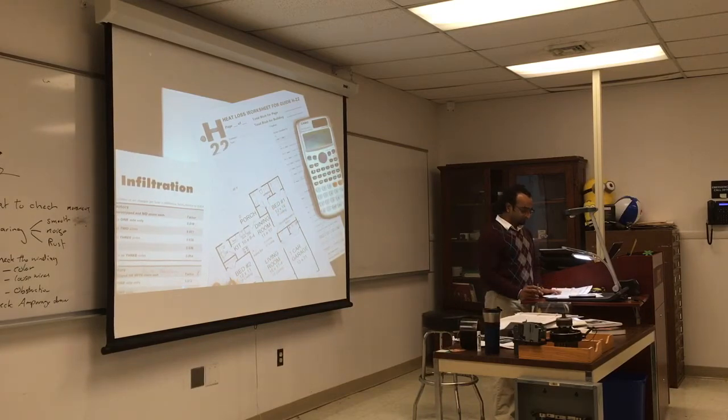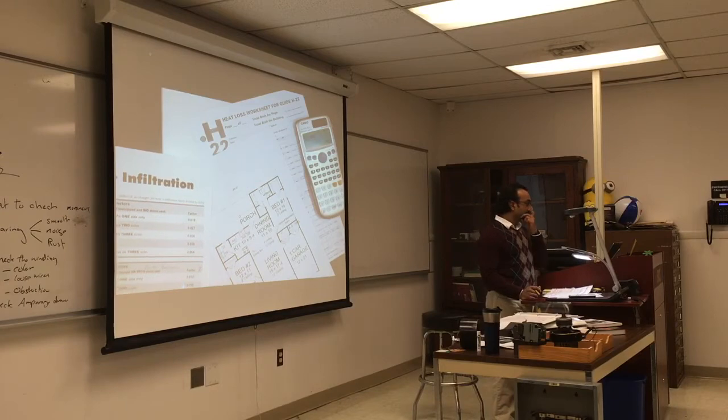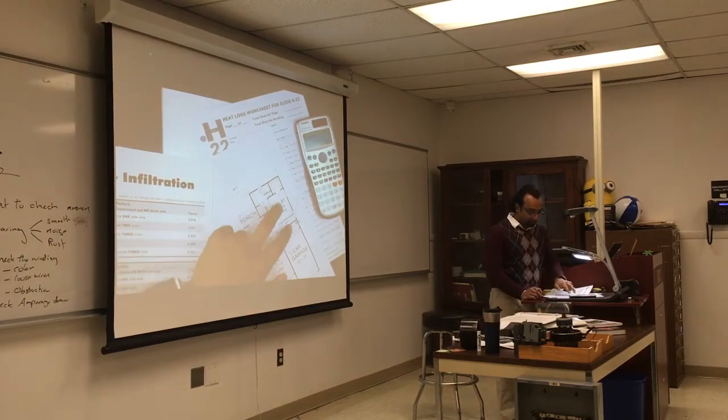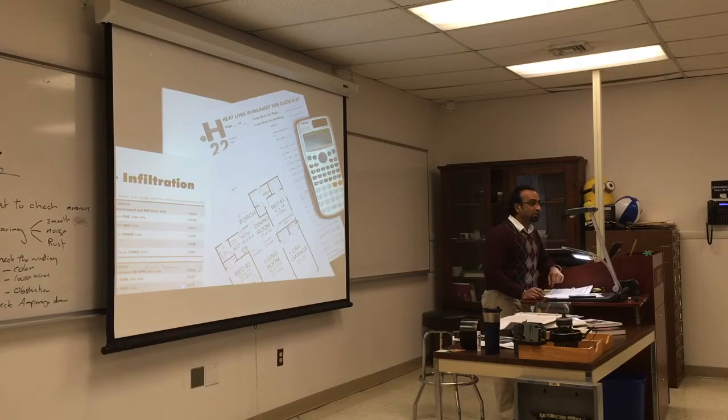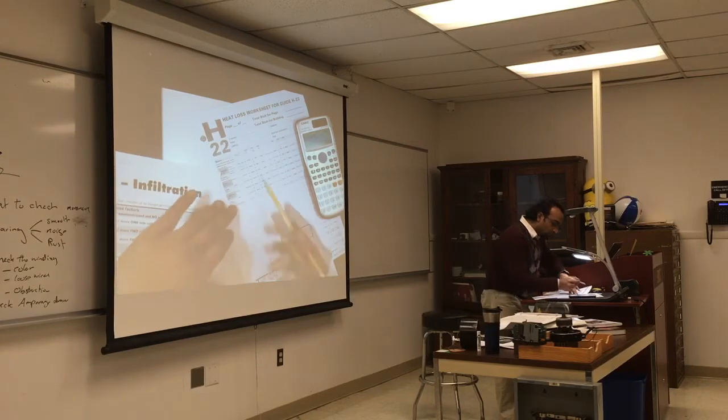Would doors to the garage be considered outside? Because sometimes the garage is not. Here it's not to the outside. Because the thing about wind and infiltration, we do not continue around that. So it's windows and doors only in one side. We're good? Yeah. So it would be the 0.012 factor. Exactly.